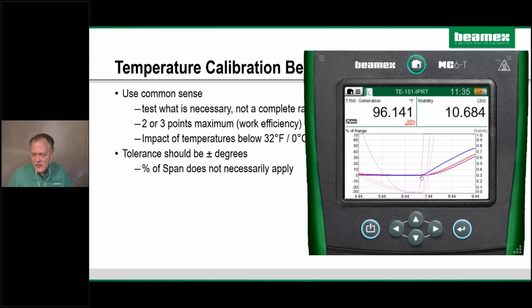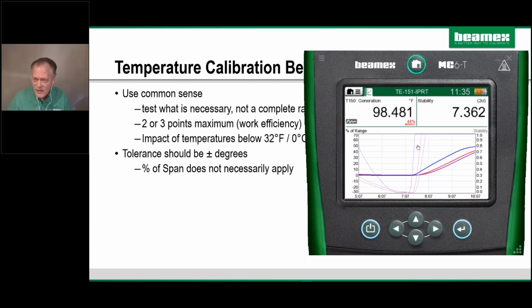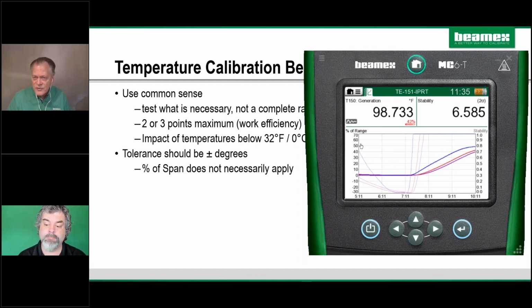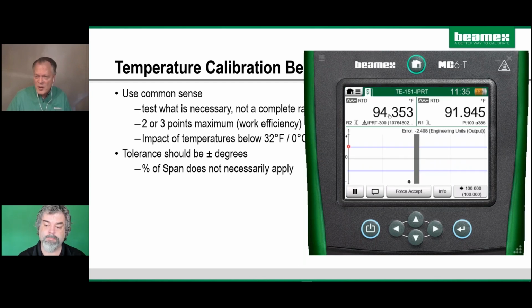We're going to see, so we took a reading at 7. We should be taking a reading somewhere around 11 or 12 minutes here. But the same phenomenon is going on. The stability is off the chart. It's up at a factor of 10 here, 10 degrees, 2 sigma. And we want to see these guys come back in, and these numbers are going to come back on the chart when these guys get closer to our 50% mark here. So the internal sensor is already there at 100 degrees, but the field probes are still lagging behind. They haven't quite even gotten to the 99 area, and they're not even on the graph. So this sensor has the zero shift going on, so we're going to ultimately end up on the upper end of the scale here for our tolerance once these guys get a little bit closer.